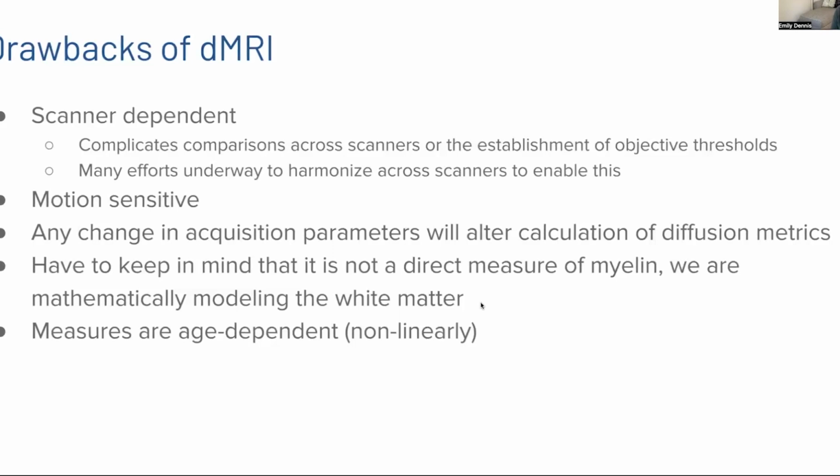Any change in the acquisition parameters will alter the calculation of the diffusion metrics. We'll talk about the specific diffusion metrics on one of the next slides, but we do need to keep the parameters consistent if we want to directly compare the measurements that we get.